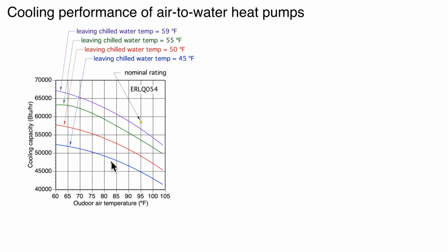If we can operate our cooling distribution system at higher chill water temperatures and still achieve proper cooling, and when I say that, I mean sensible cooling and moisture removal. We don't want to just cool air and not dehumidify it. We're not going to create comfortable conditions. But through sizing the coil in an air handler, it's possible to run systems at 50, even 55 degree chill water temperatures. And you can see that makes quite a difference in the cooling capacity of this particular unit.